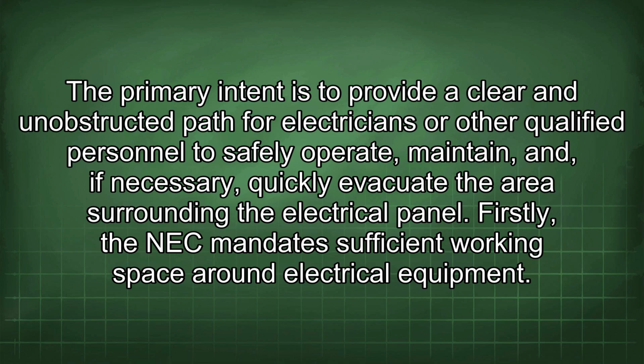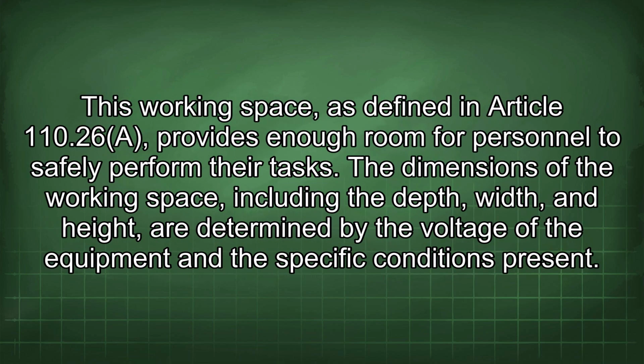Firstly, the NEC mandates sufficient working space around electrical equipment. This working space, as defined in Article 110.26a, provides enough room for personnel to safely perform their tasks. The dimensions of the working space, including the depth, width, and height, are determined by the voltage of the equipment and the specific conditions present.